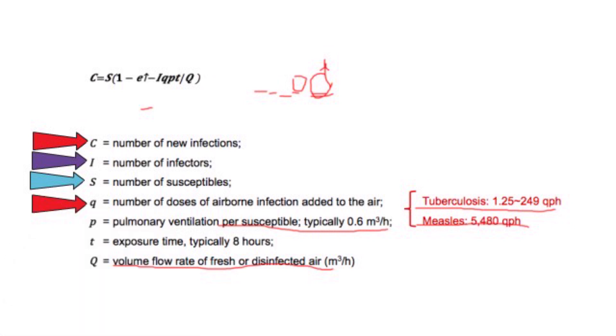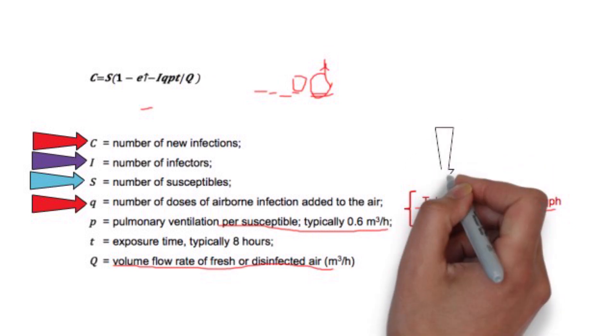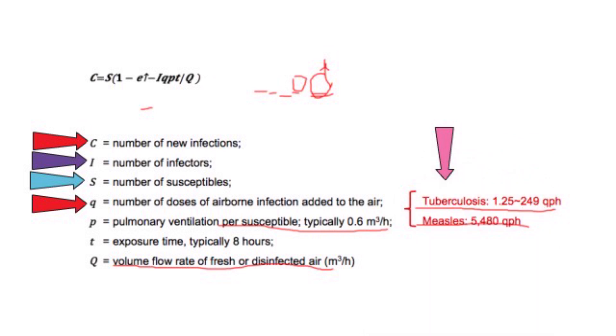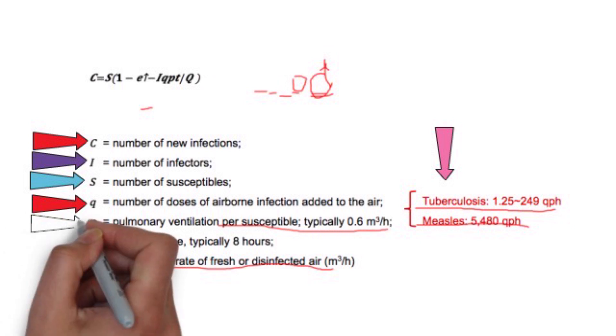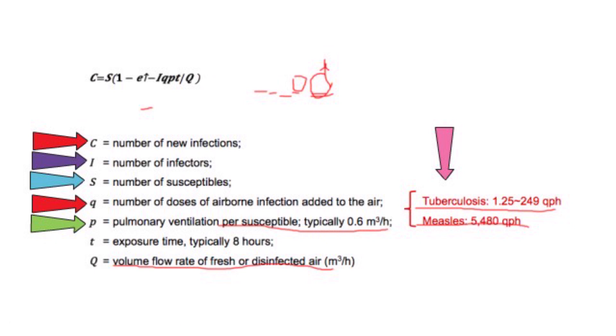The Q value depends on the type of infectious disease. The more infectious the disease is, the higher the Q value. For example, for tuberculosis, Q ranges from 1.25 to 249 quanta per hour. But for measles, this value could be as high as 5,480. P is pulmonary ventilation per susceptible and is mostly a fixed value. T is exposure time, meaning how long you have been around the infected patient.